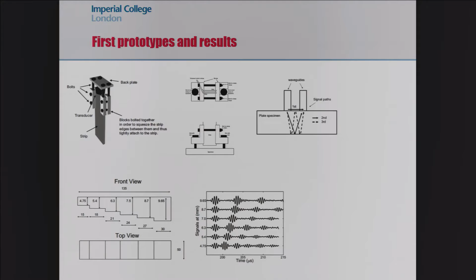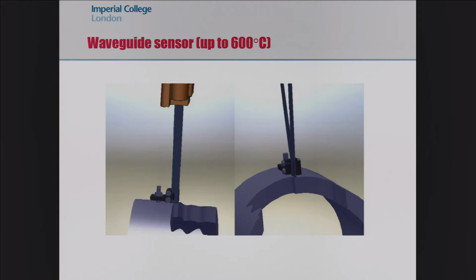As I said, we had the backing of BP, who were interested in installing these things in their plant. So we were able to develop a full wireless sensor that contained the wireless head, which has a battery, an electronics card, a wireless send-receive module, and also the transducers. We could attach that to the top of the waveguide and launch a wave into the material, with a simple clamp that is bolted on via stud welds onto the pipe material. Then these waves bounce up and down in the pipe wall, and we can measure the travel time and thereby the thickness of the component.